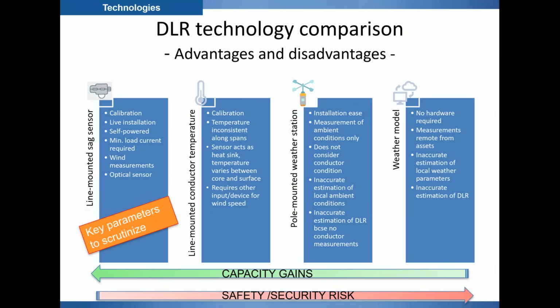Next option is to be a bit more precise and to install weather stations along the line, which could give you a reading of the prevailing weather parameters on that line. But again, they would be as accurate as the weather station would be, and obviously it depends on the number of weather stations that you can afford to have along the line. And the more the better, obviously, but you will still not have any input on the true behavior of the conductor. So it's basically like an open loop system.